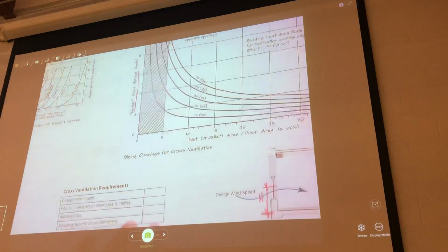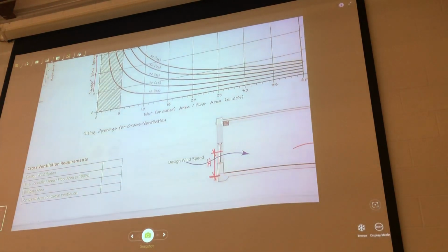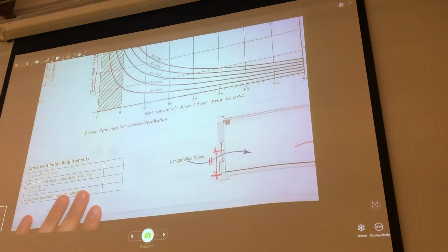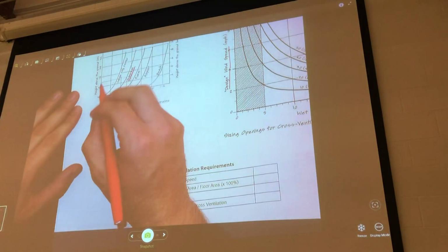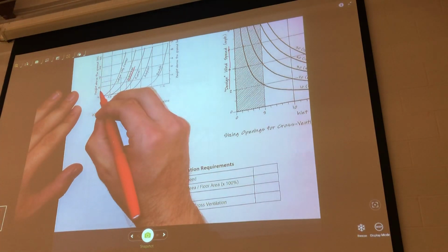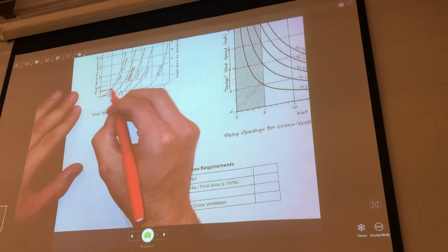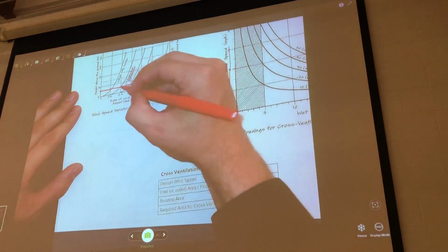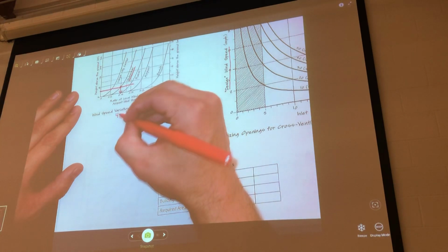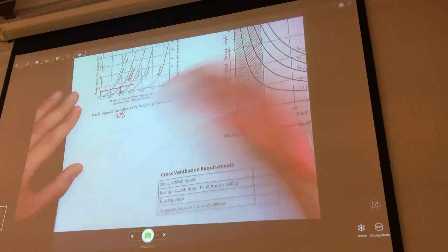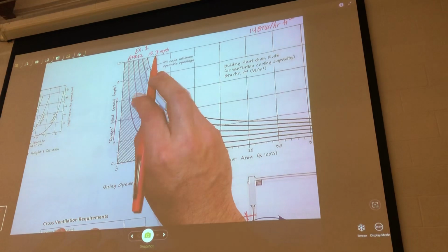All right. Now, how high are our windows? I really don't care, just throw a number out. 5 feet? I'm okay with that, so 5 feet. So 0 to 8 feet, we're going to be just above halfway. Draw our line straight across. Where we intersect suburban, go straight down. So I'm going to say we're at about 40% of our actual measurable wind speed.